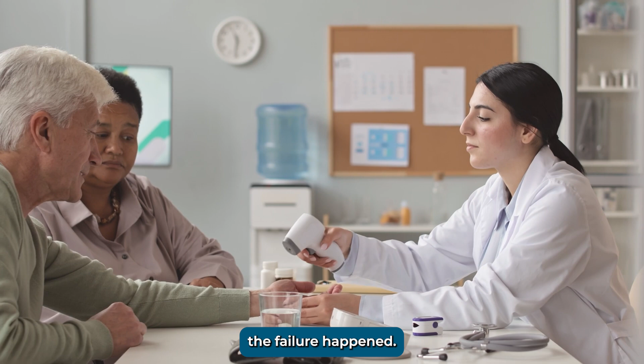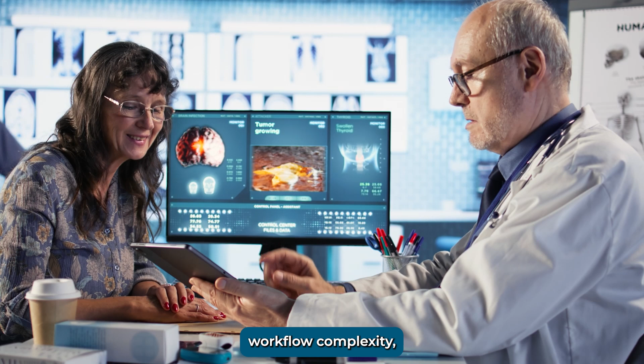Good root cause analysis goes deeper than the obvious answer. If an adhesive bond failed, was the issue surface preparation, cure time, humidity, operator technique, fixture alignment, material lot variability, or an uncontrolled supplier change? If a pump drifted out of accuracy, was the issue component wear, software compensation, calibration interval, sensor aging, or use conditions that were never fully tested? If users keep making the same mistake, is the problem training, labeling, interface design, workflow complexity, or a use-related hazard that should have been designed out earlier?